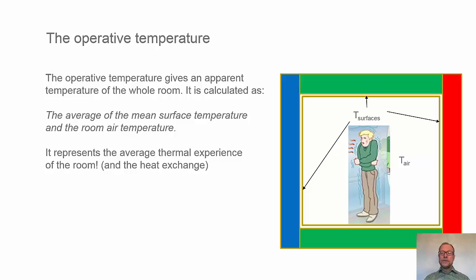The operative temperature is a way of finding an apparent room temperature which takes both the longwave radiation and convection into account. So the operative temperature is calculated as the average of the mean surface temperature and the room air temperature. It represents the average thermal experience of the room, which is basically a heat exchange with the surrounding room.